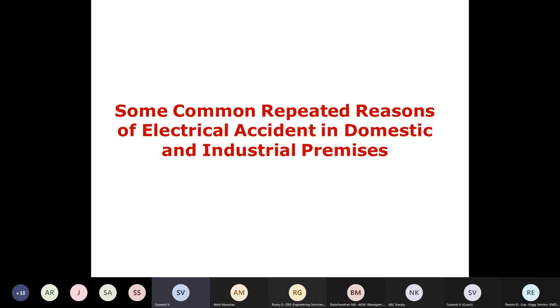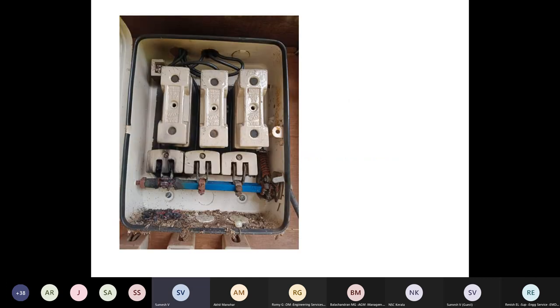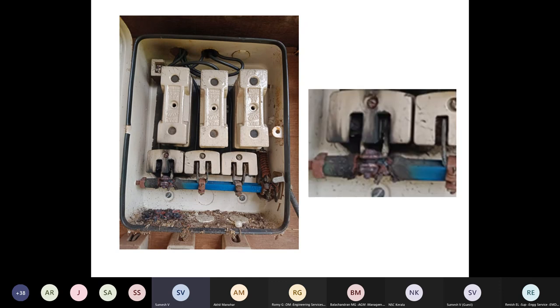Some common repeated reasons of electrical accidents in domestic and industrial premises. This is one of the major accident points that happens in domestic and industrial premises. This is the main switch that we call the main switch, provided at the incomer of the consumer premises. The common problem with this type of switch is that the ebonite rod burns. Because of the insulation, the ebonite rod gets damaged, and supply is coming to the body of the switch. If someone touches this switch, he will get an electric shock. Many accidents are reported because of this reason.